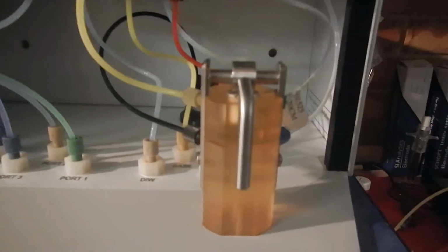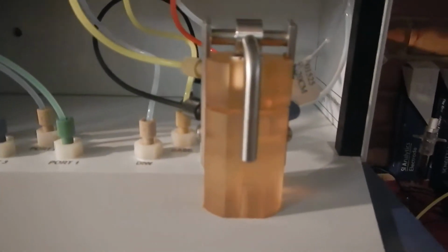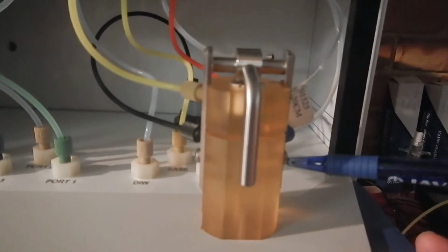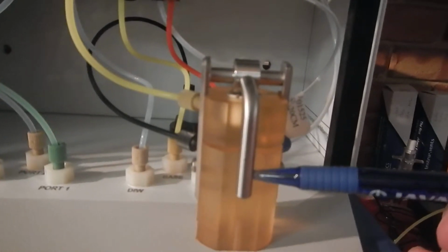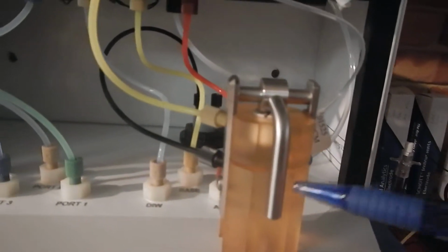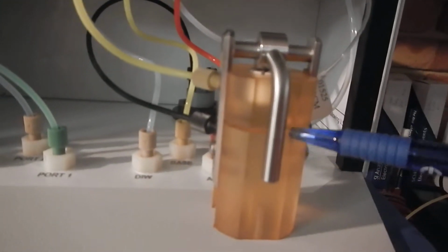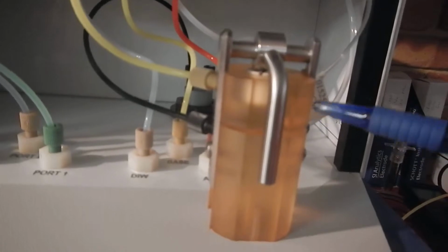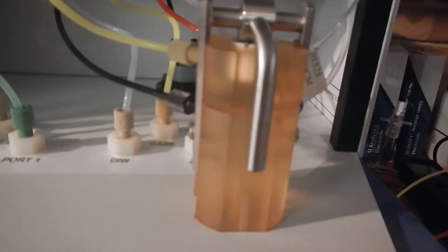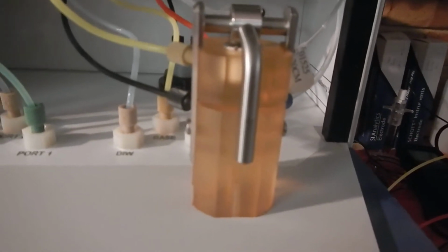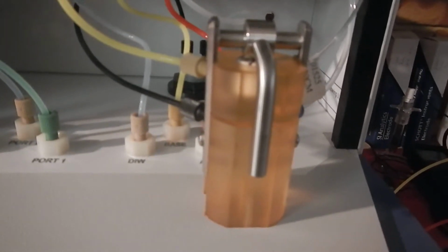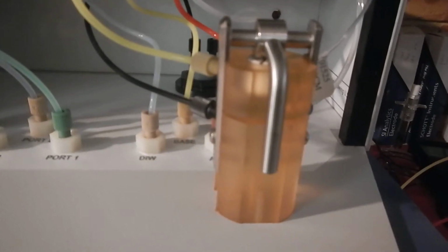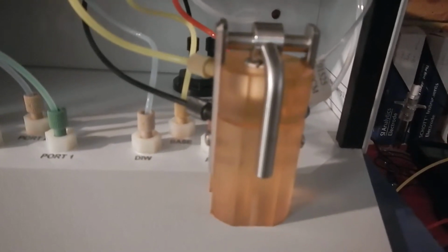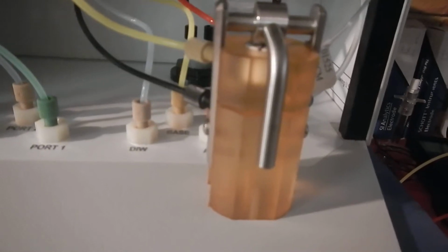The machine uses a gas diffusion module through which we flow hydrochloric acid in the strength of 0.1 molar up to 2 molar. This allows an acidified sample to produce hydrogen cyanide gas, which flows across a membrane into a capturing solution of 0.1 molar sodium hydroxide. This eliminates many interferences and is a direct copy of the well-known laboratory gas diffusion system sold by OI to many gold labs and other labs around the world.